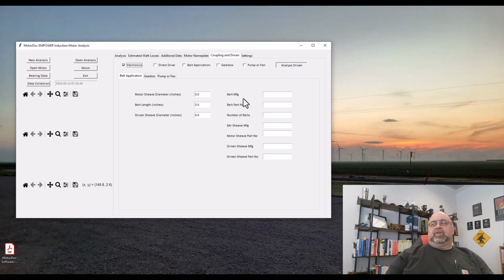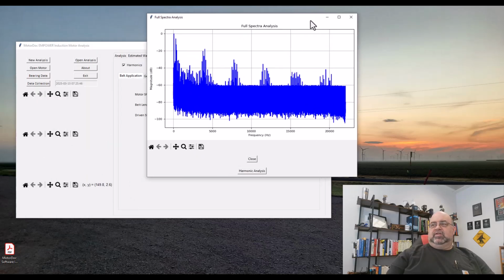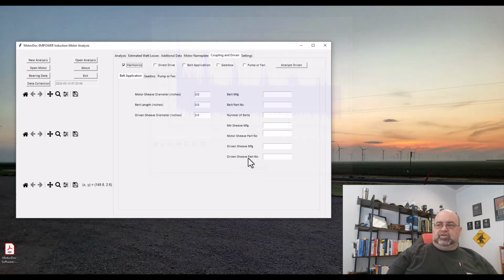All that current and any voltage that's being induced as well is sitting on the surface of the machine. So where they thought they might have had 60 volts on the shaft reference to the frame of the motor, it's very possible that it's the opposite. Here's that same set of harmonics. As you can see, this allowed me to troubleshoot certain things.